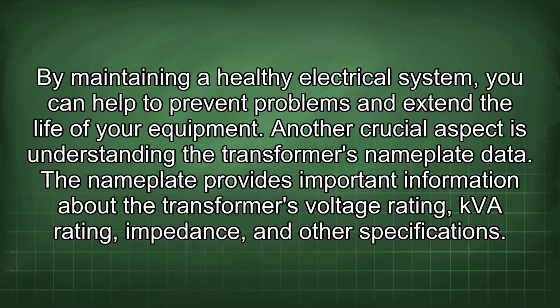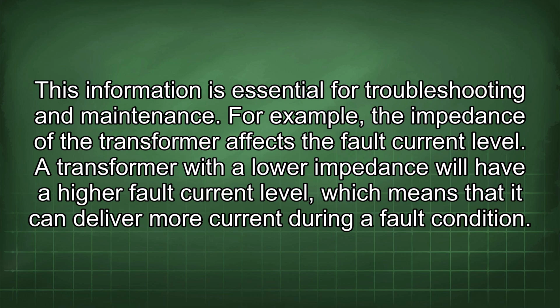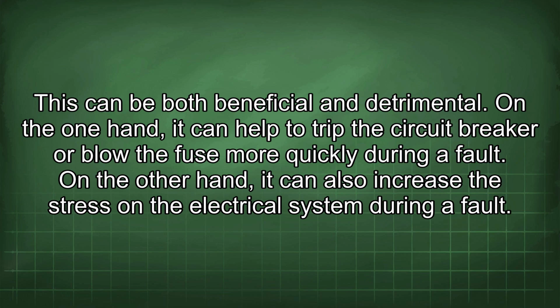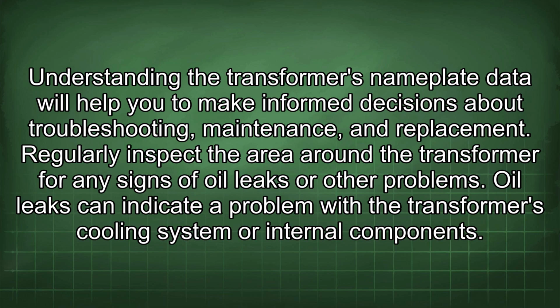Another crucial aspect is understanding the transformer's nameplate data. The nameplate provides important information about the transformer's voltage rating, kVA rating, impedance, and other specifications. This information is essential for troubleshooting and maintenance. For example, the impedance of the transformer affects the fault current level. A transformer with a lower impedance will have a higher fault current level, which means that it can deliver more current during a fault condition. This can be both beneficial and detrimental. On the one hand, it can help to trip the circuit breaker or blow the fuse more quickly during a fault. On the other hand, it can also increase the stress on the electrical system during a fault. Understanding the transformer's nameplate data will help you to make informed decisions about troubleshooting, maintenance, and replacement.